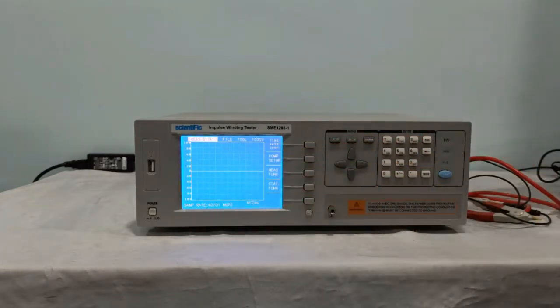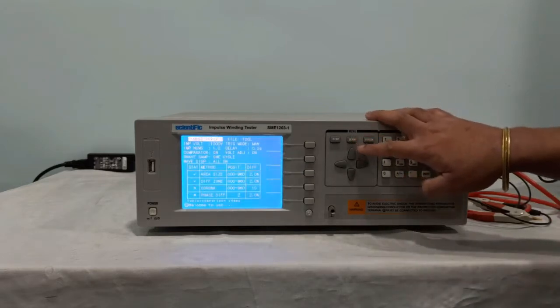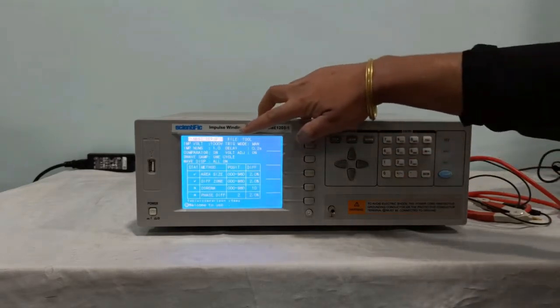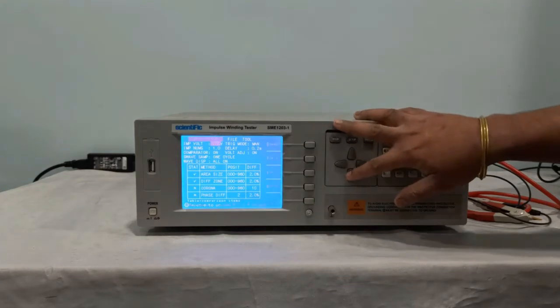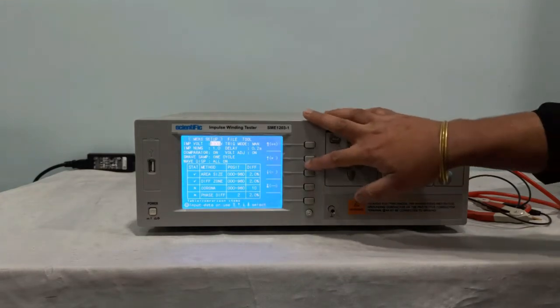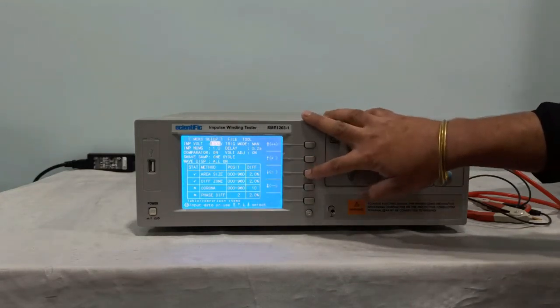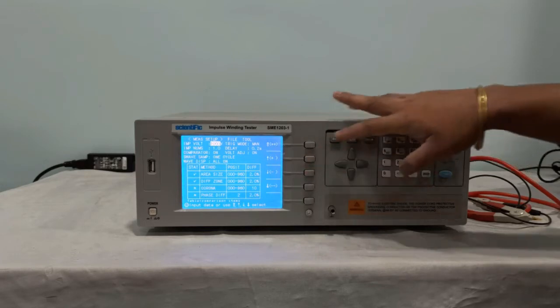So before testing we need to create a standard waveform, and in order to create the standard waveform we need to do some settings. So we'll go to setup. Now in setup, first what we find is impulse voltage. Here you can input the impulse voltage. You can increment or decrement using this plus minus keys.